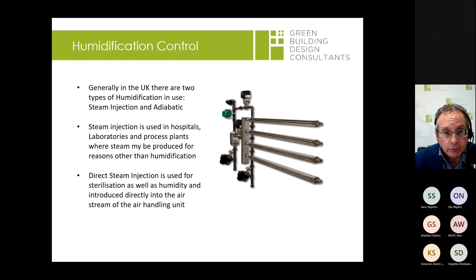I've just popped in a slide that shows the other options you've got, where it's basically done in a box, and then there are some pipes that connect to the AHU. This one here is gas generated, so it's cheaper to run. Obviously, gas is about a quarter of the cost of electricity. And this one here is resistive electrical steam generation, so it uses electricity, like your boiling of the kettle, and then it goes in. And again, we would be recommending this type of thing now would come with RO water, which is very, very clean, to stop scaling and help on maintenance.